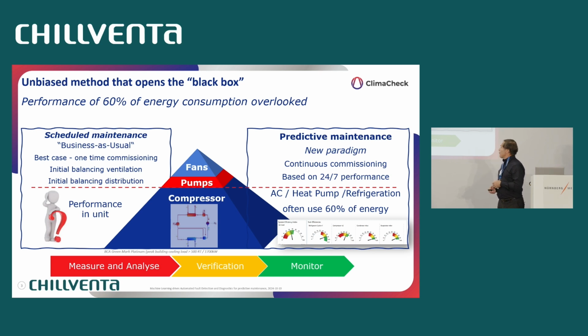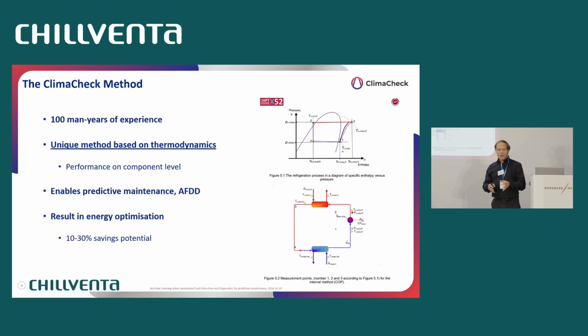downtime. So what we do is that we apply thermodynamics. We measure the refrigeration process, which makes it possible to, in 20 minutes, hook up the sensors and have COP, condenser efficiency, compressor efficiency, everything at the same level as a test rig at a manufacturer's site. So we have supplied about 50 manufacturers with development test rig analytics. So I promise you it works.